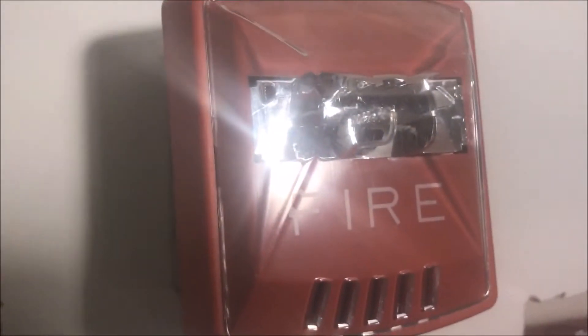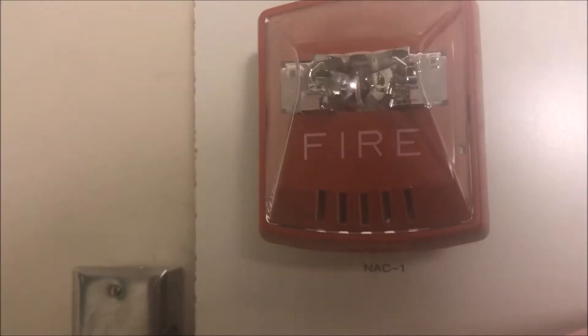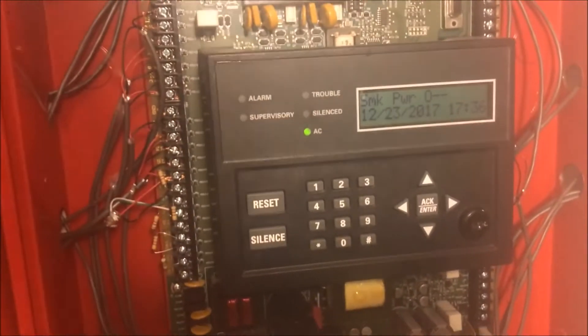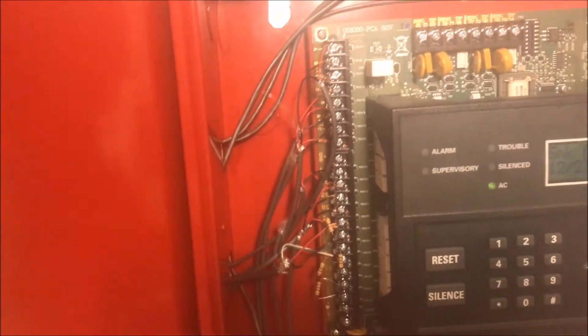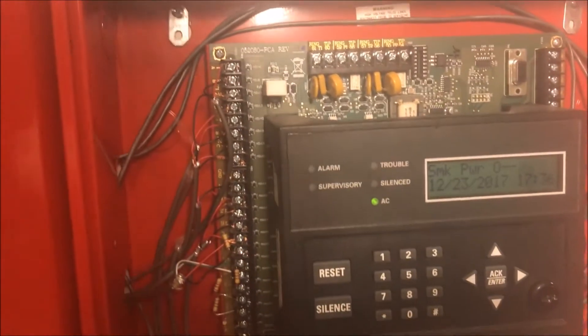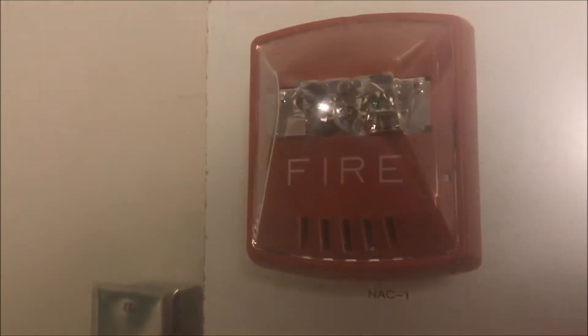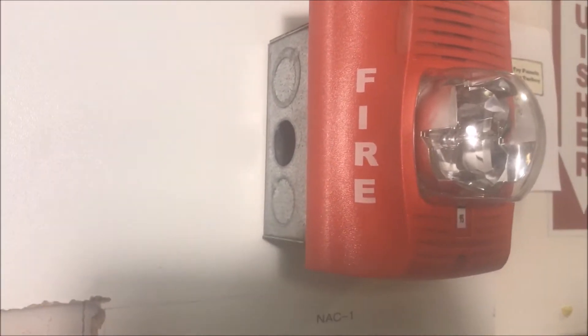What? It's doing Code 3? It's doing Code 3. Why? You are probably thinking it's because it's in Wheelock Sync and it's going to do Code 3 — but that's not what it's set on. And this other alarm isn't doing Code 3. So it's not like the panel is coding out Code 3. It's for some reason thinking it should do Code 3.